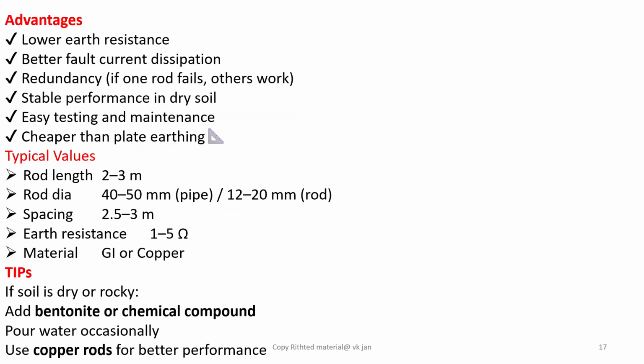Friends, the advantages of tripod earthing are lower earth resistance, better fault current dissipation, redundancy if one rod fails, the other works, stable performance in dry soil, easy testing and maintenance, and it is cheaper than plate earthing. Typical values: rod length 2 to 3 meter, rod diameter 40 to 50 mm pipe or 12 to 20 mm in rod shape. Spacing is 2.5 to 3 meter. Earth resistance 1 to 5 ohm. Material may be GI or copper. This is used if soil is dry and rocky. Add bentonite or chemical compound. Pour water occasionally. Use copper rod for better performance.